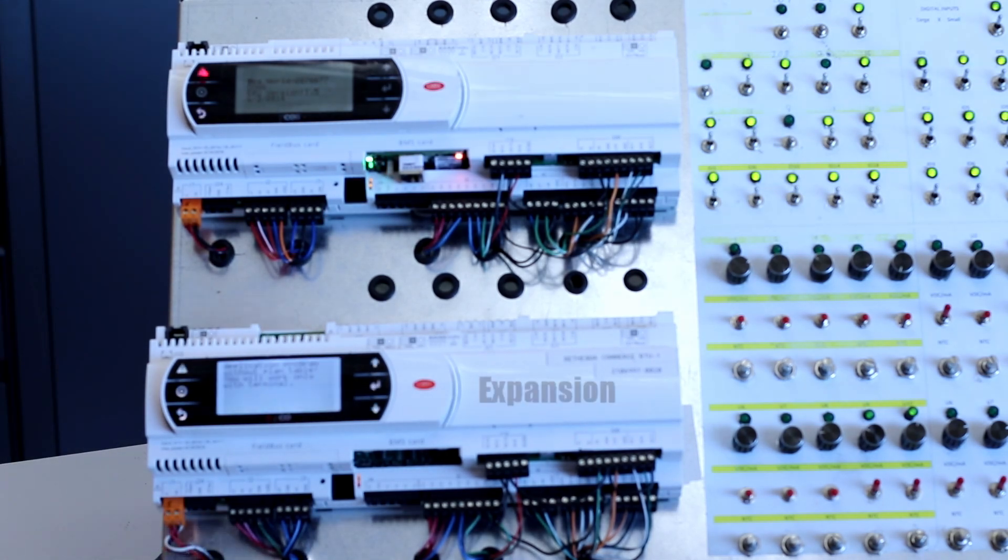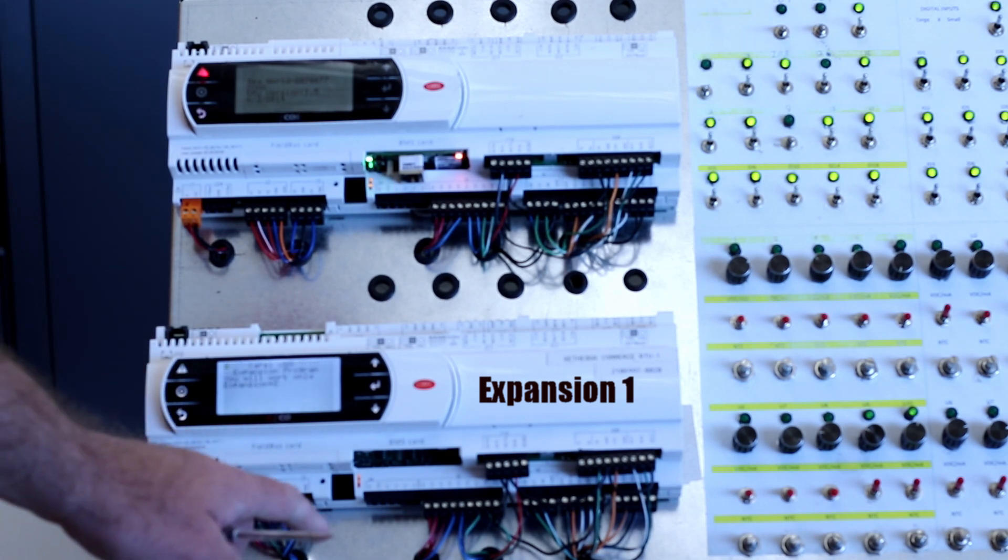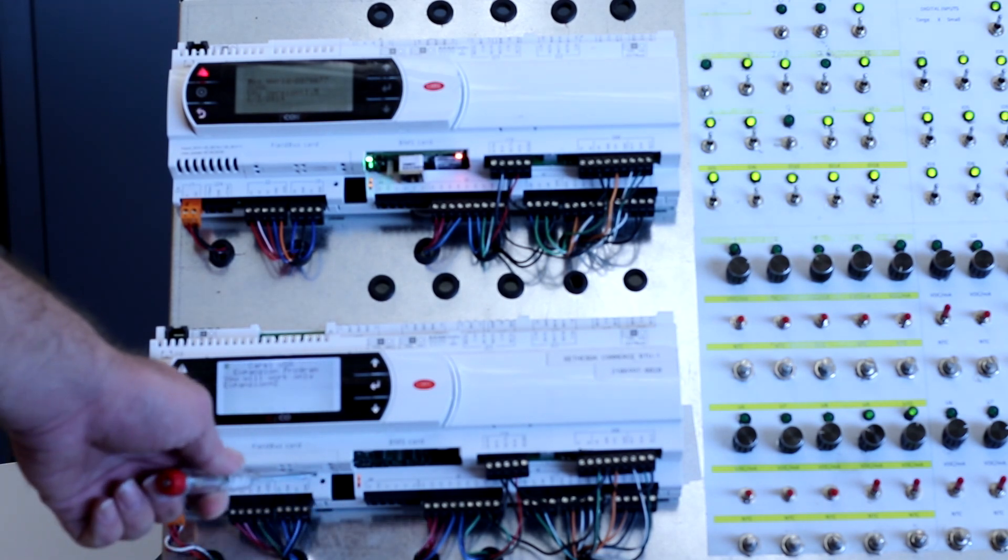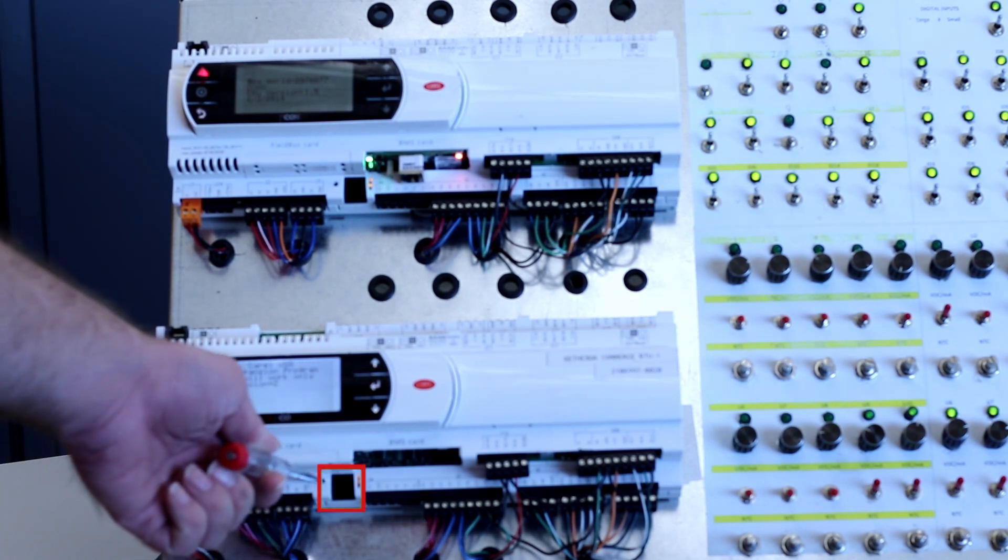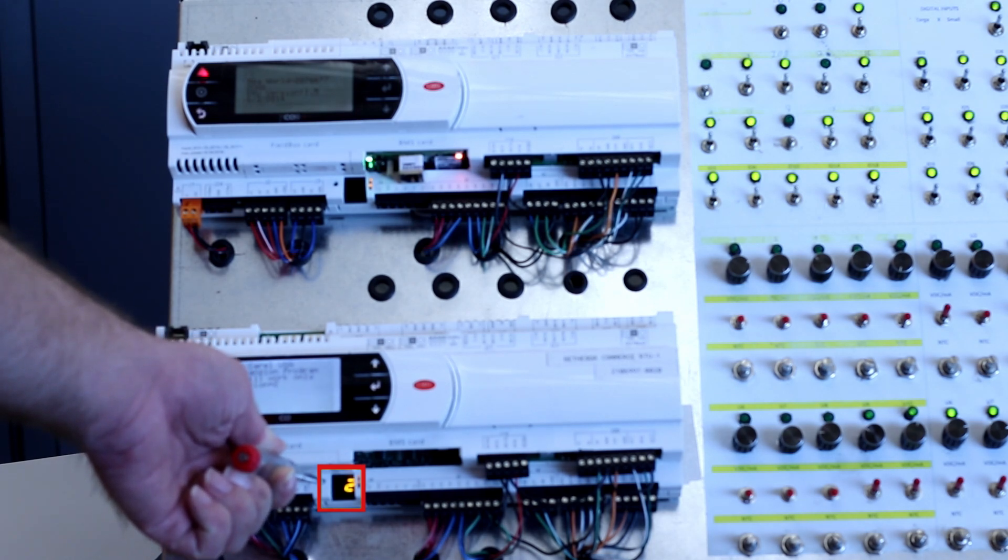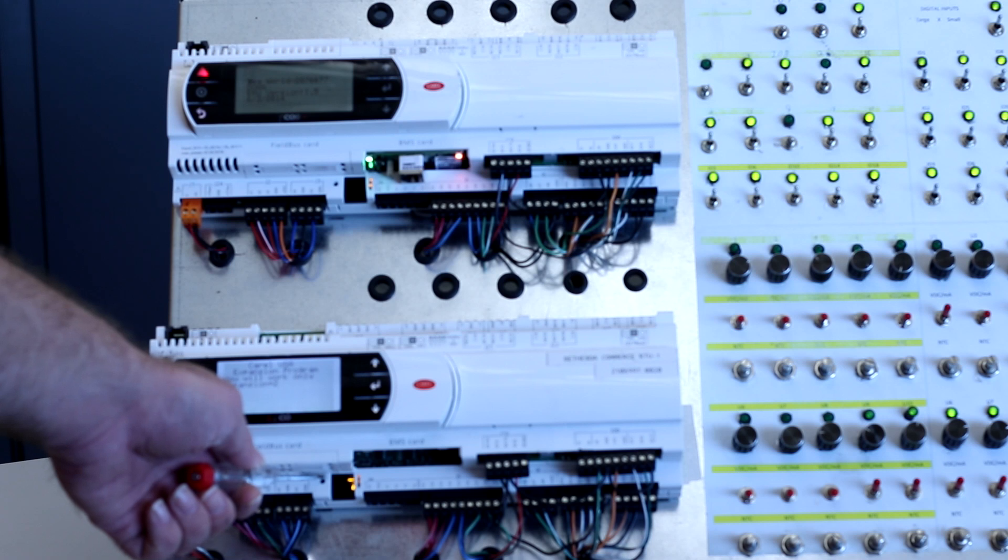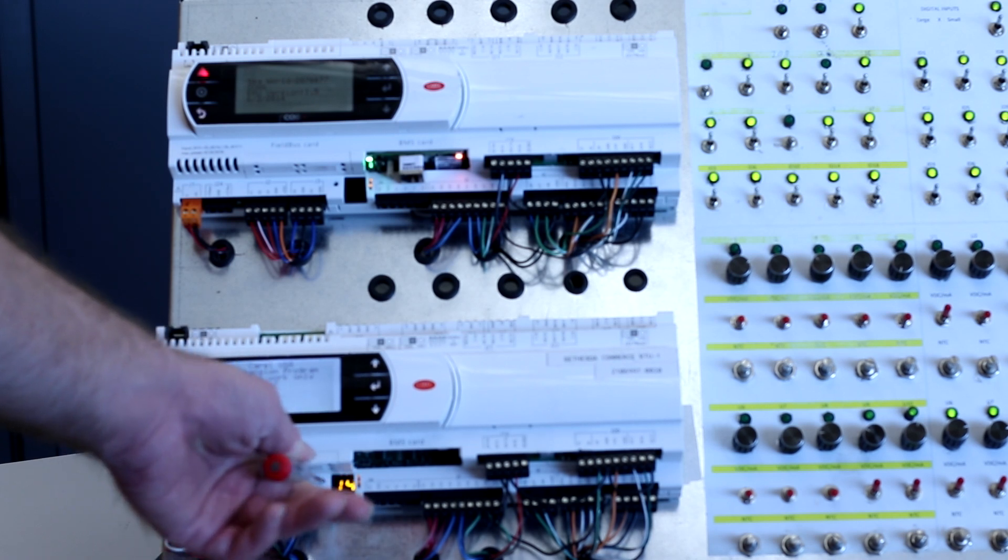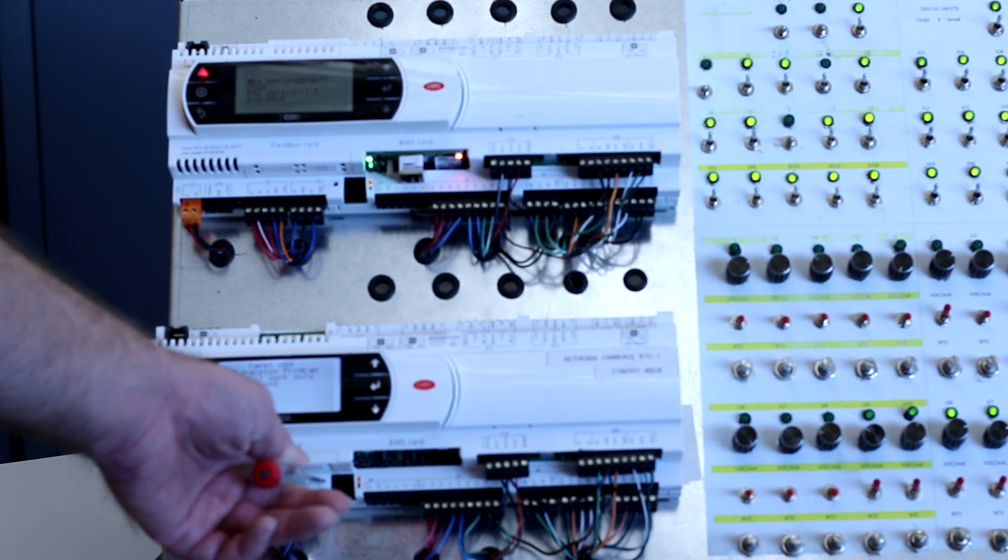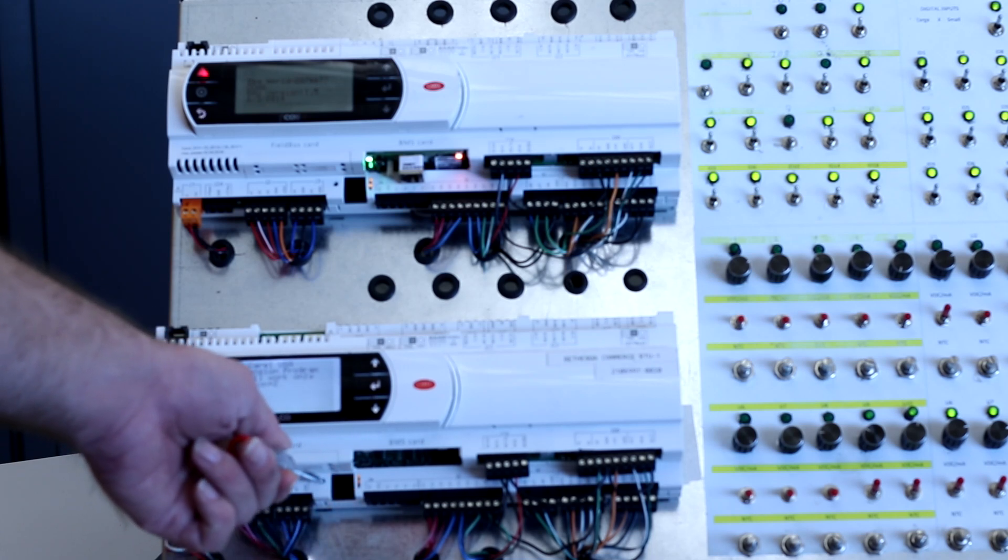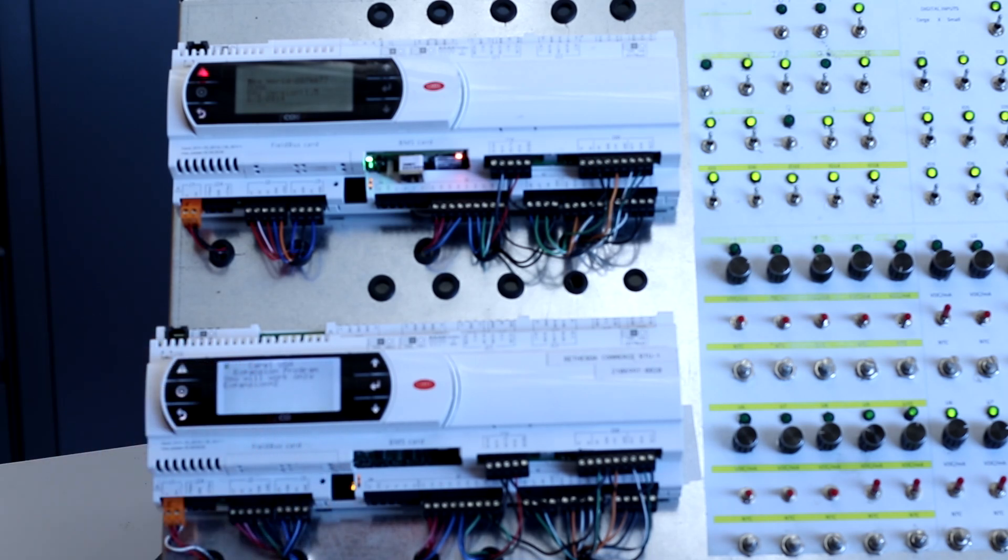The lower board in this example will be used as expansion 1, so we will change the address to 1. Hold the button for a few seconds until the number begins to blink. You can now change the number by pressing the button repeatedly or holding it down. Once the correct number is selected, leave it displayed for about 10 seconds. You will see the number start to blink much faster.